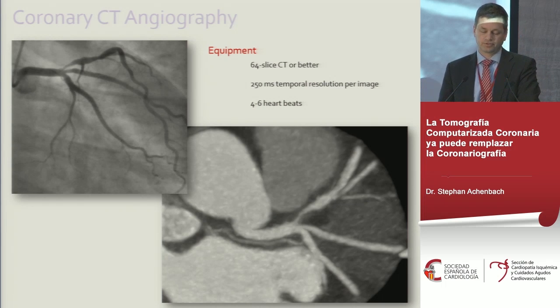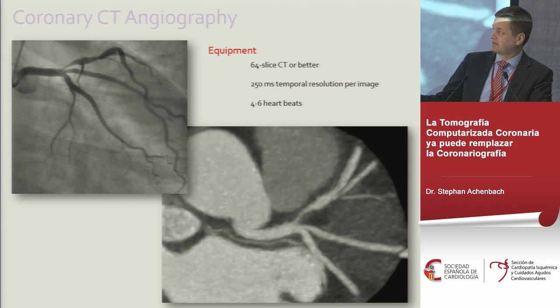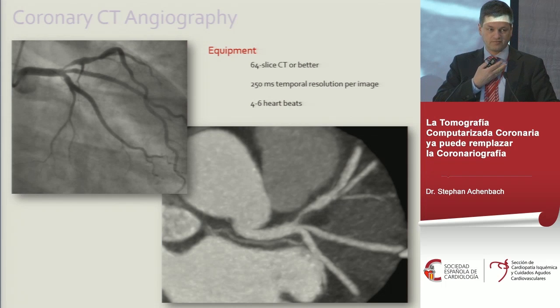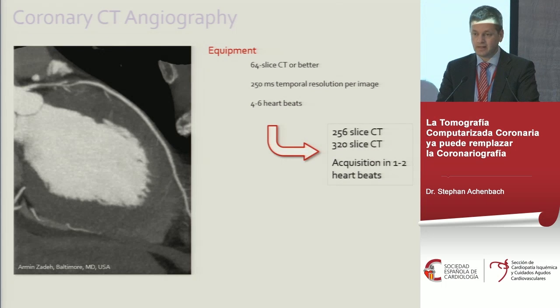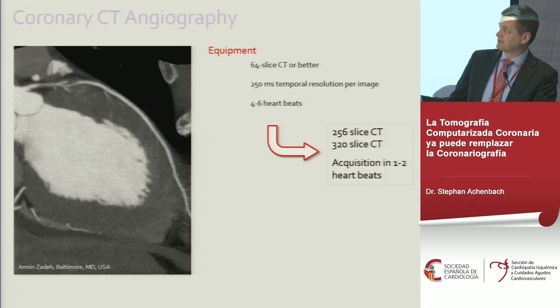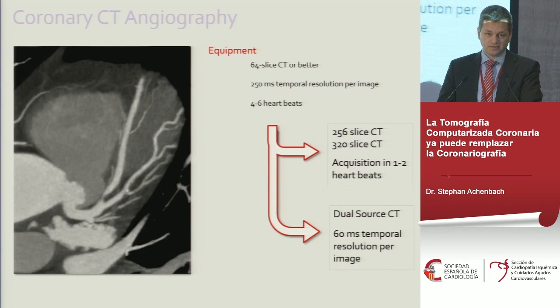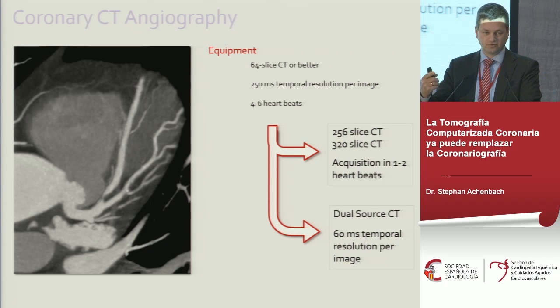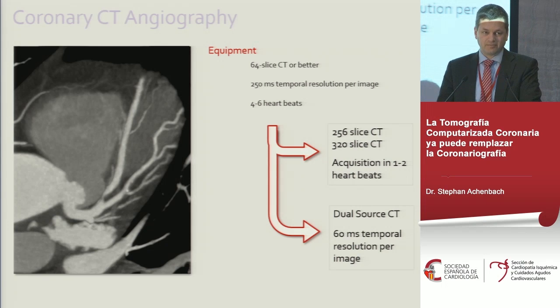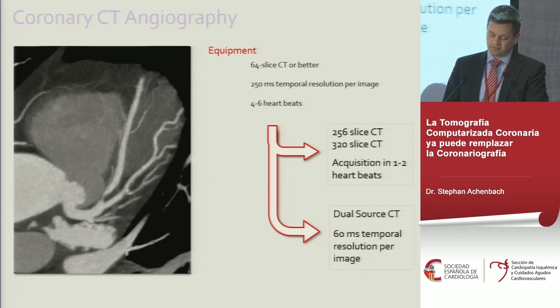The minimum prerequisite is a 64-slice CT scanner, providing temporal resolution of approximately 250 milliseconds requiring four to six heartbeats to cover the heart volume. More modern scanners with 256 or 320 slices can cover the heart in one or two heartbeats. Dual-source CT combines two tubes and two detectors in one gantry, improving temporal resolution dramatically — the most modern dual-source scanners achieve 60 milliseconds per image, far better than the 250 milliseconds of 64-slice scanners.